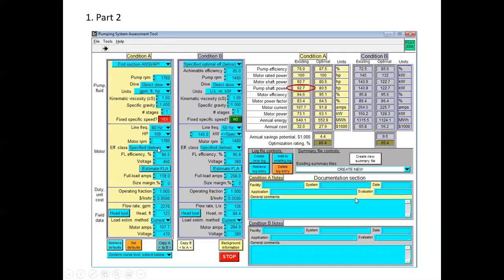We specify, so you click the pull down box and click specify the efficiency, and 94.5. We put in 460 on the volts. I didn't estimate because we were given a full load amps of 118, and we didn't say anything about a service factor. I don't think that's going to change anything. So I put in 0. If it operates all the time, I think that was information, at 5 cent electricity will give us a cost.